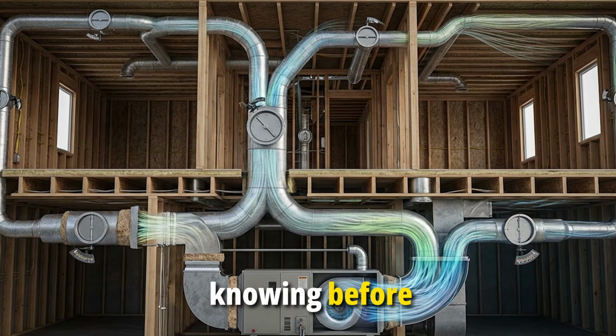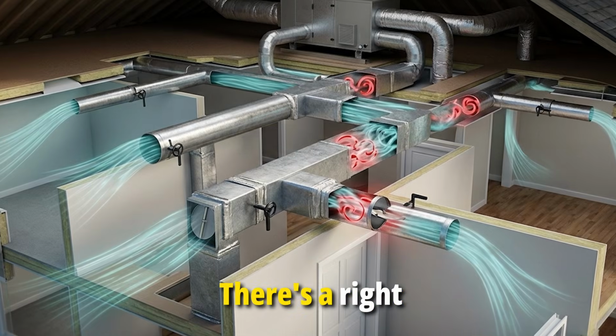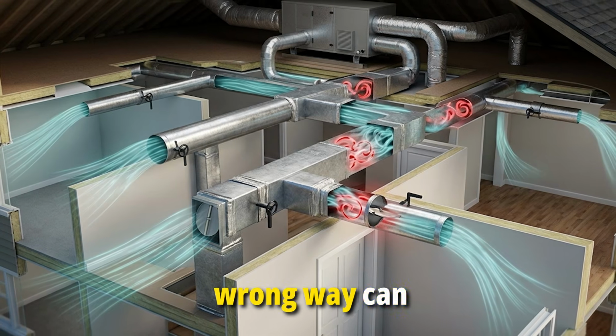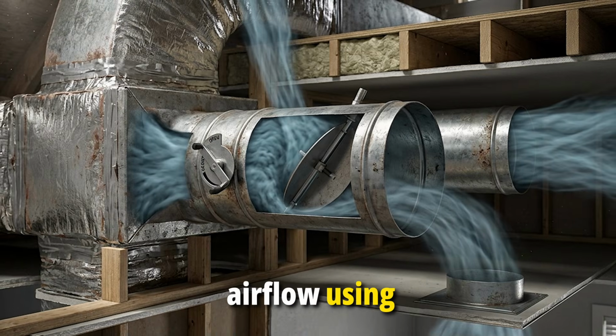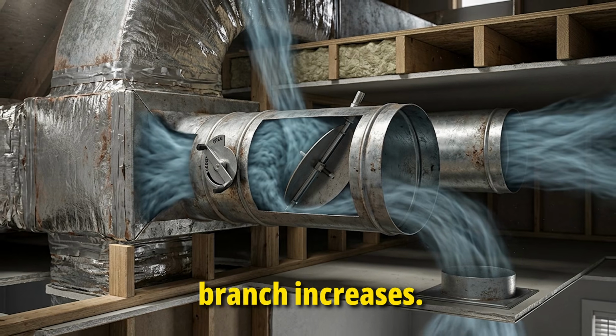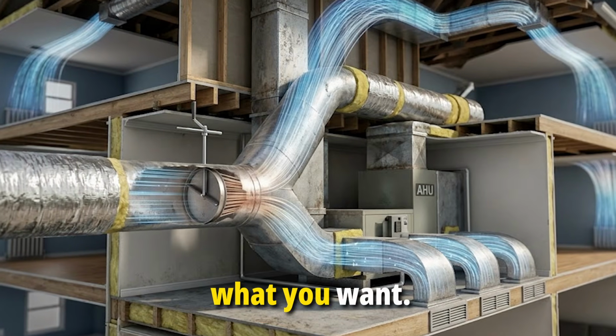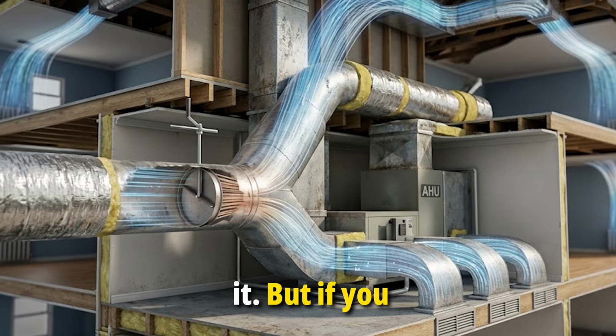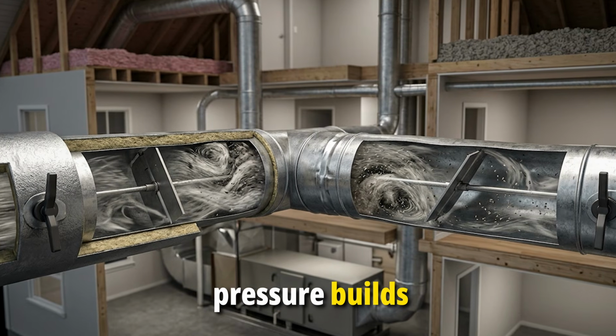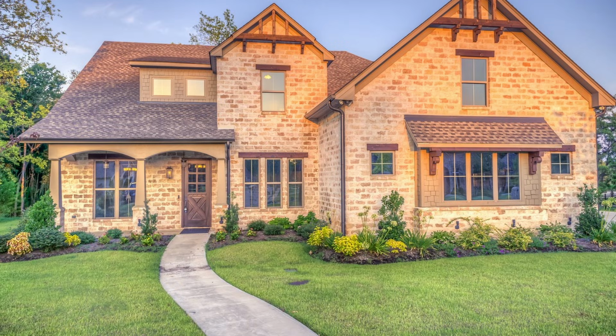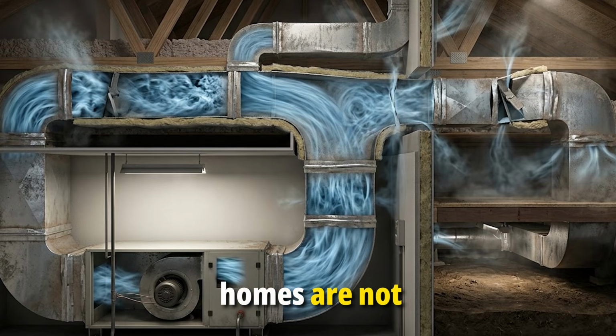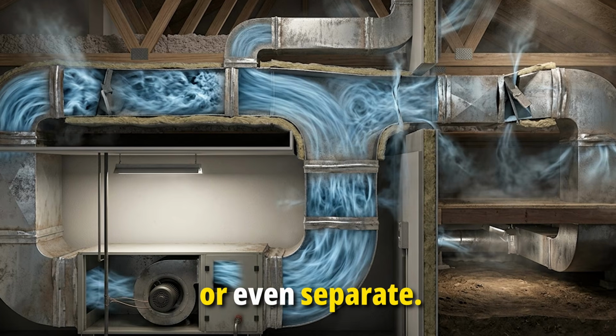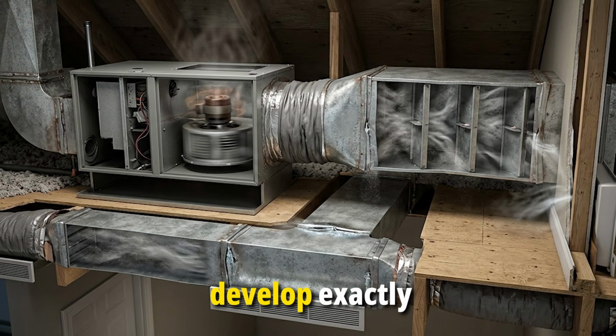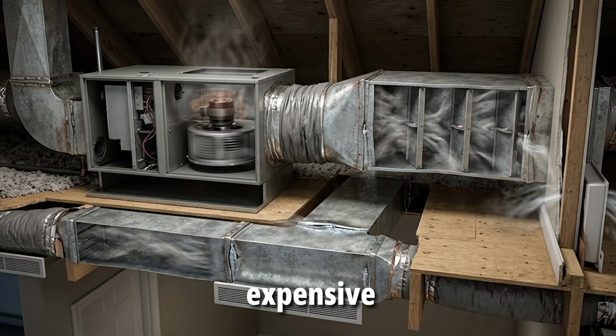But here is something worth knowing before you touch a single one. There's a right way to do this and a wrong way, and the wrong way can cause real problems. When you restrict airflow using dampers, pressure inside that duct branch increases. A moderate increase is exactly what you want. It pushes more air toward the rooms that need it. But if you close dampers too aggressively, pressure builds beyond what the system was designed for. What happens then? A few things, none of them good. Your blower motor works harder against the resistance. Duct seams, which in most homes are not perfectly sealed, can start to leak or even separate. And your air handler can develop exactly the kind of problems that generate a very expensive service call.